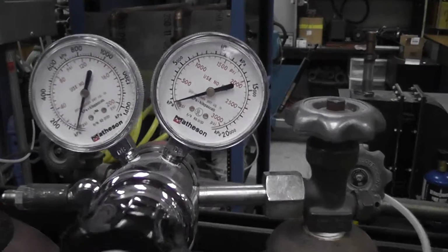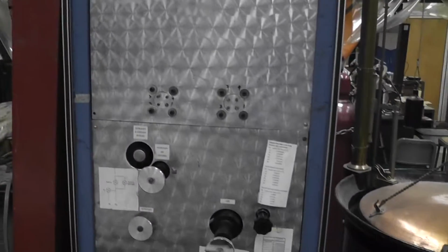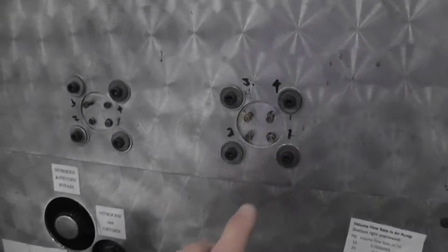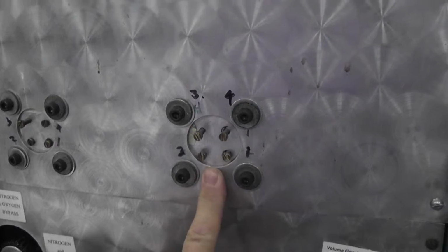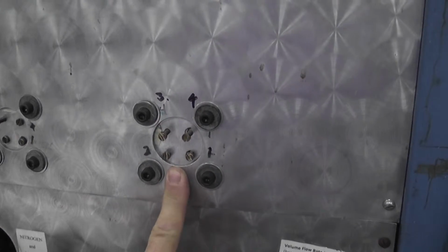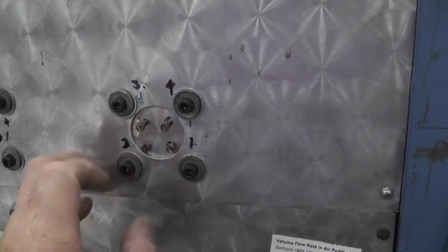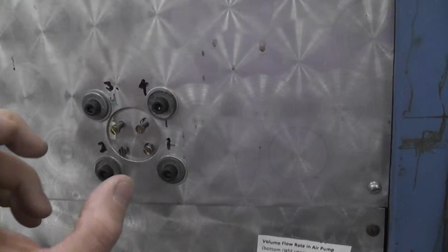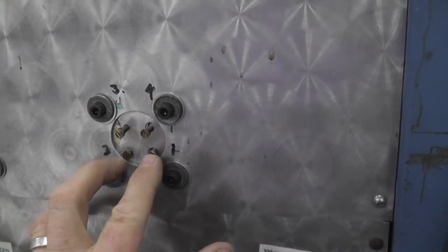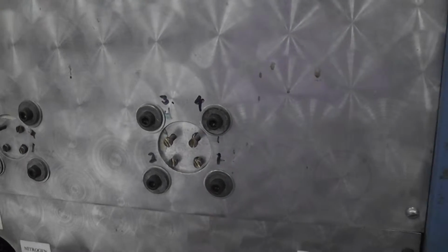Great. Okay, here is another assembly for measuring flow rates. You can see again, you have some gauges. This one's a little uglier, but these are your orifice plates right here. And in this particular assembly, what you're seeing is these screws control little Teflon plugs that go into holes in the orifice plate. So you can have one or more holes open, and then you would calibrate this thing for the number of holes that are open. And you can see these are all numbered 1, 2, 3, and 4.